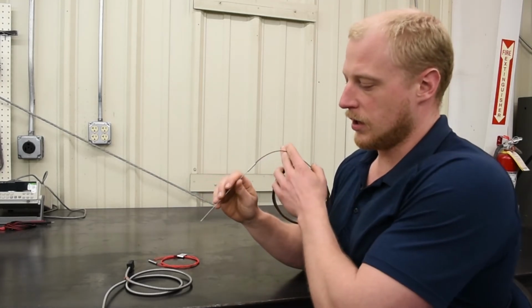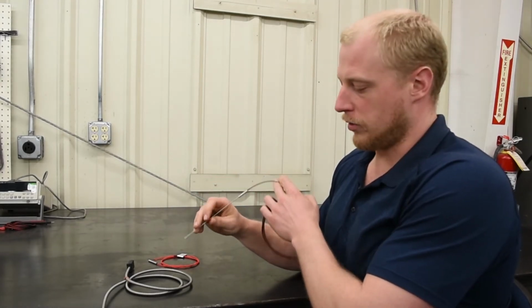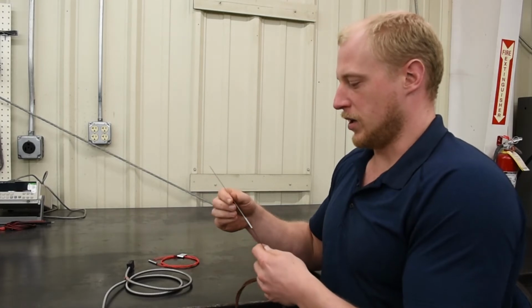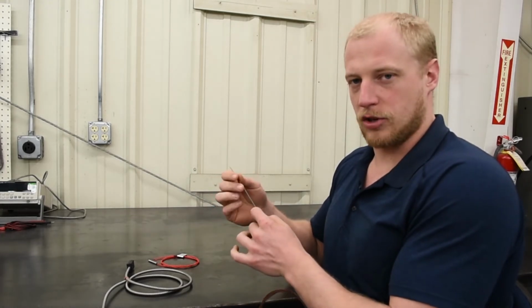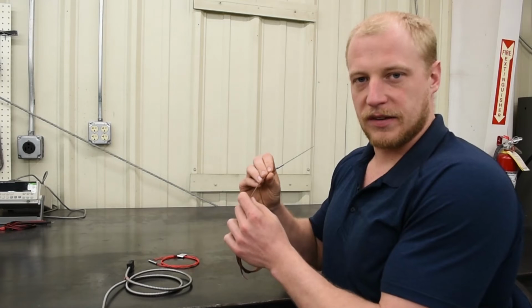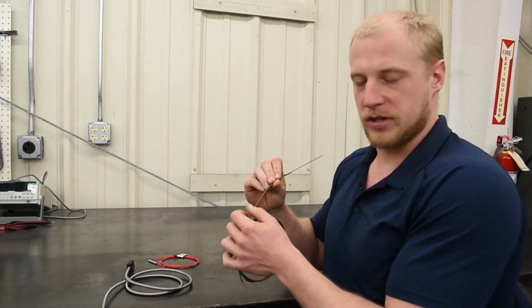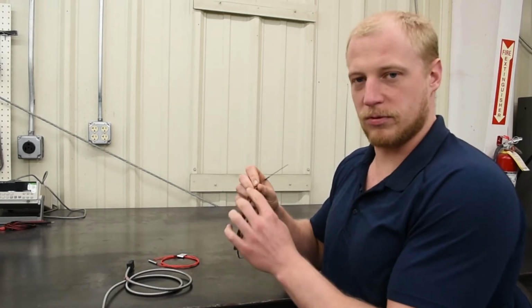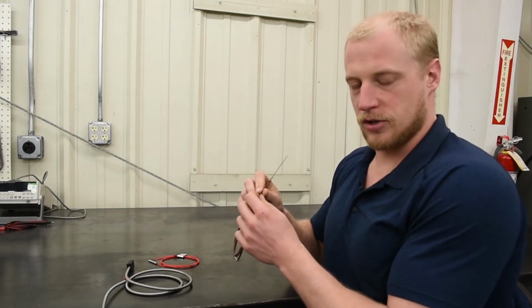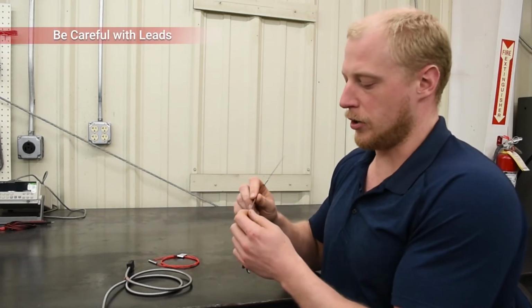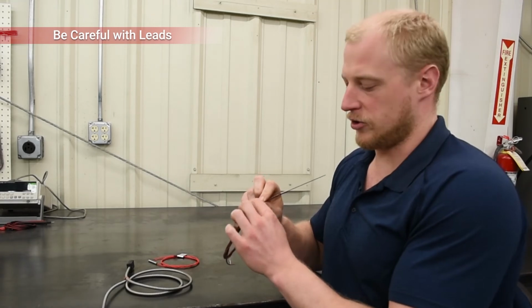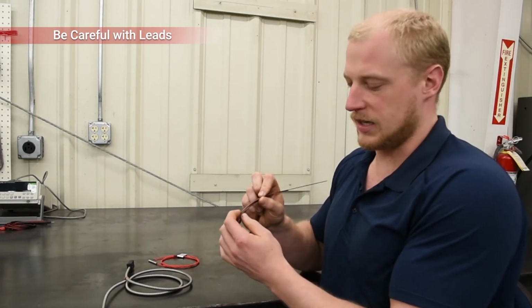It should go into the bottom of a long bore or something like that, but don't bend this probe at sharp angles. This particular model also has Teflon leads, which are good for moisture protection but not as durable or strong as the metal hose, so you don't want to cut, scratch, or damage these leads.